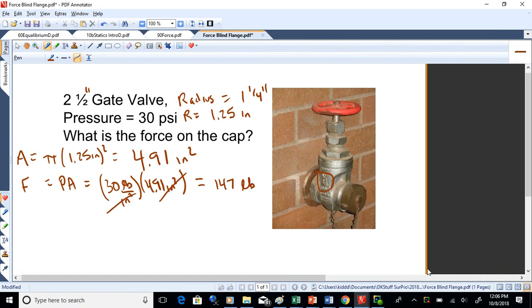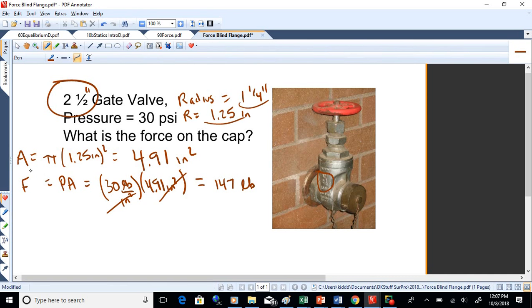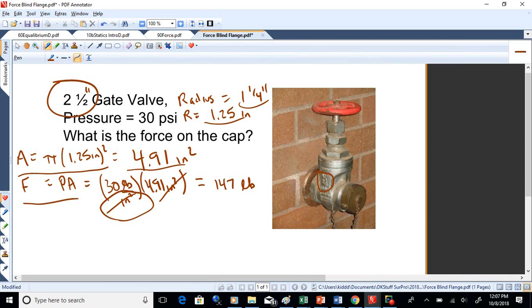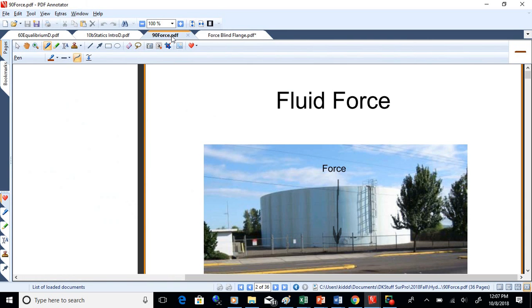We just went through an example in class: a two-and-a-half inch gate valve at 30 psi. We want to find the force on that cap. Since it's round, we call it out by diameter, so the radius is 1.25 inches. The area is pi times 1.25 squared, which is 4.91 square inches. Then F equals PA: 30 pounds per square inch times 4.91 square inches gives us 147 pounds.